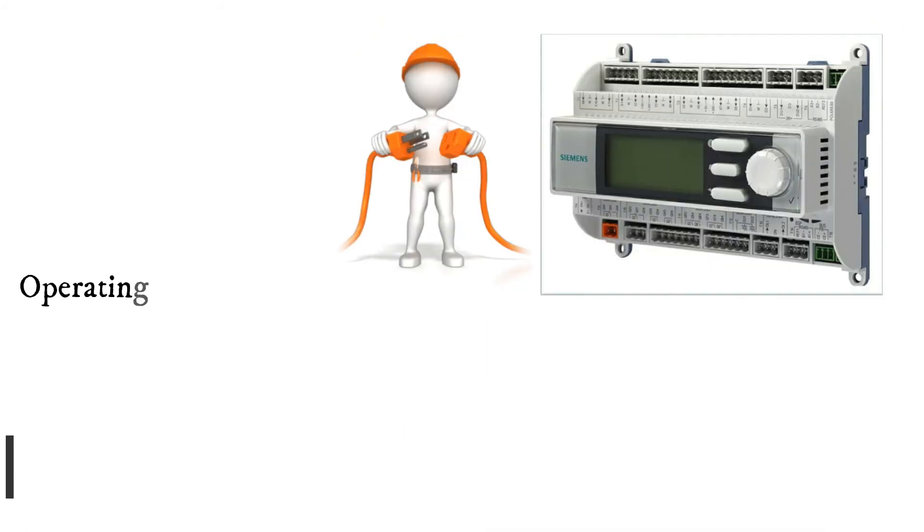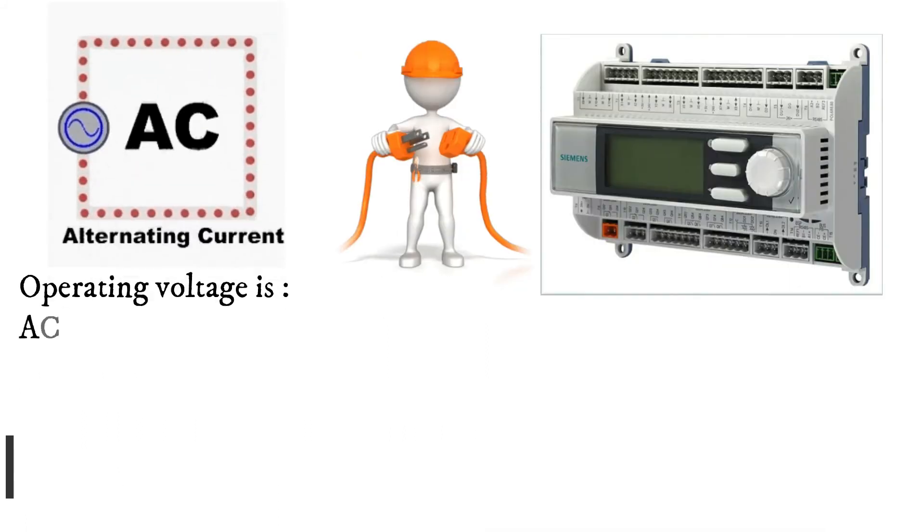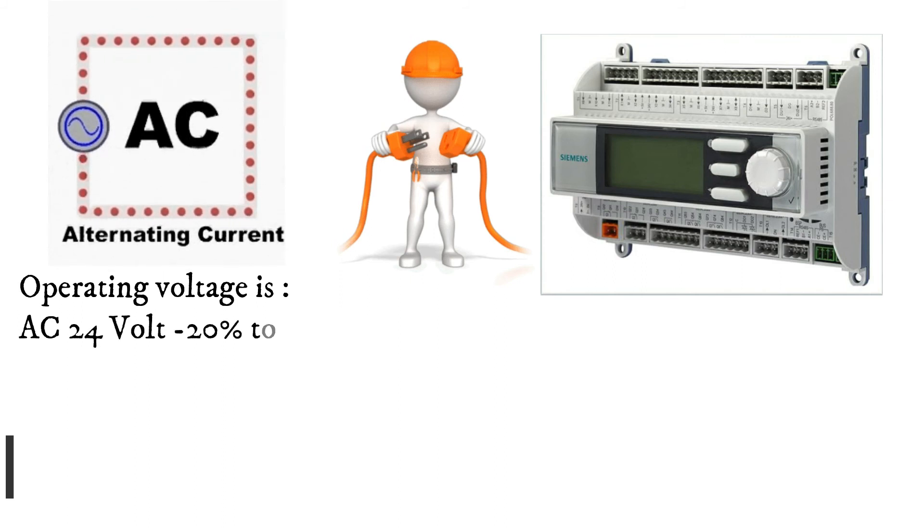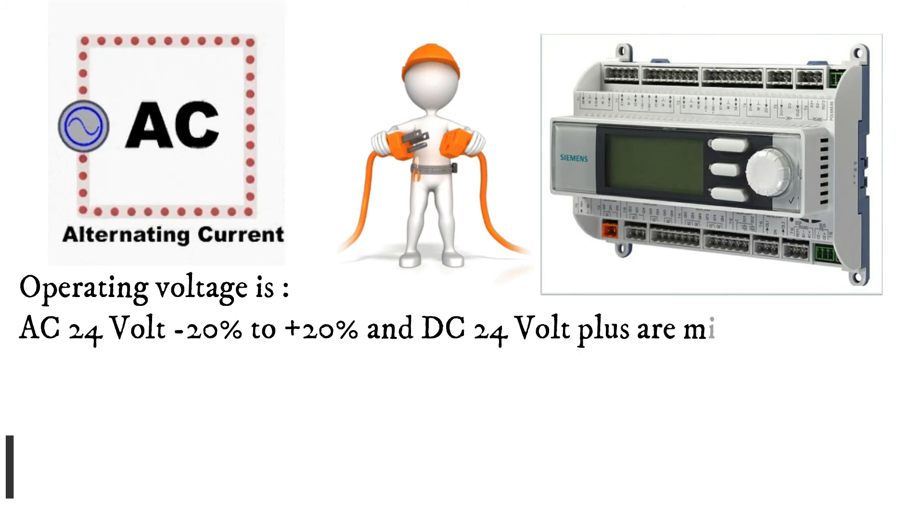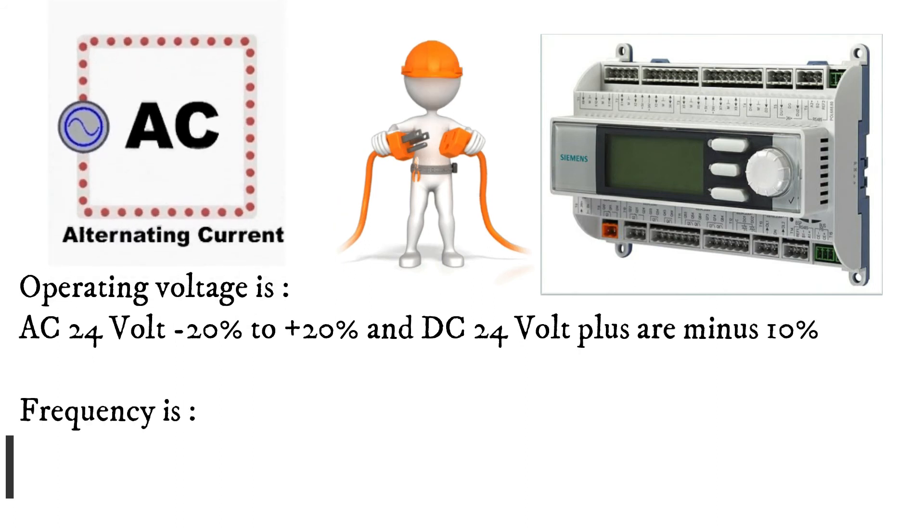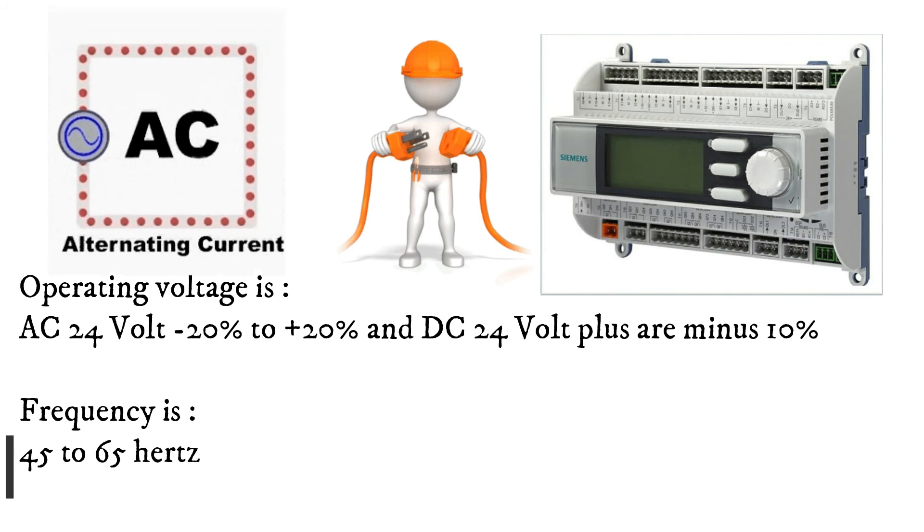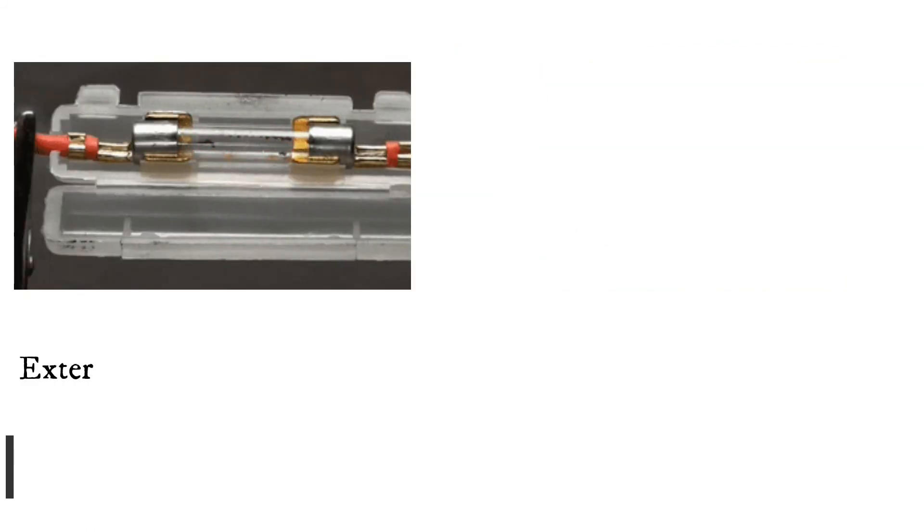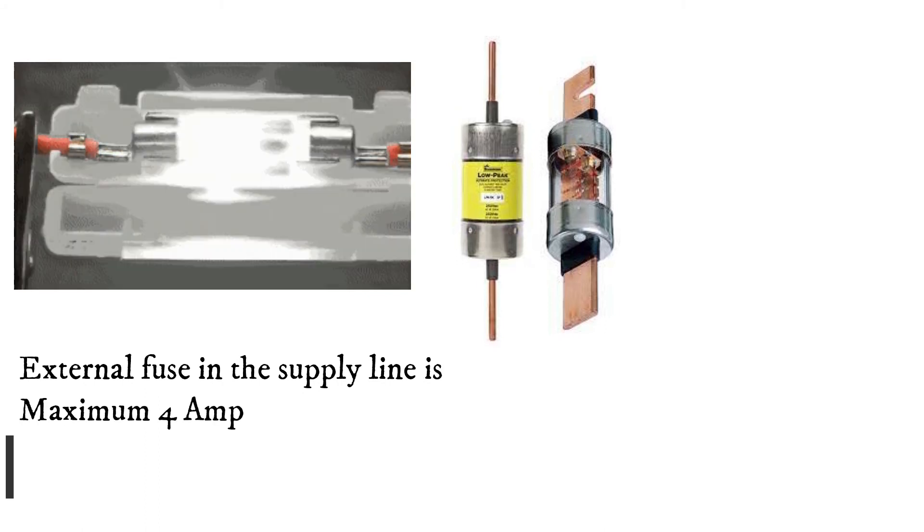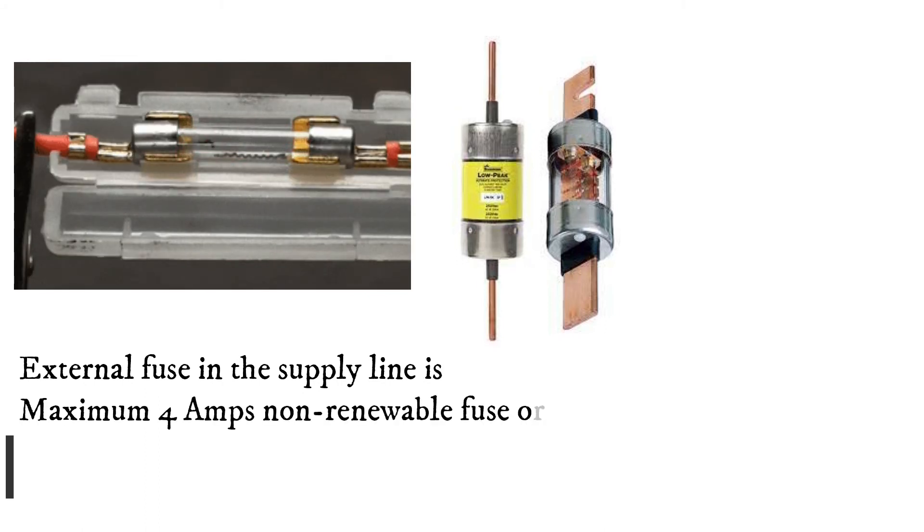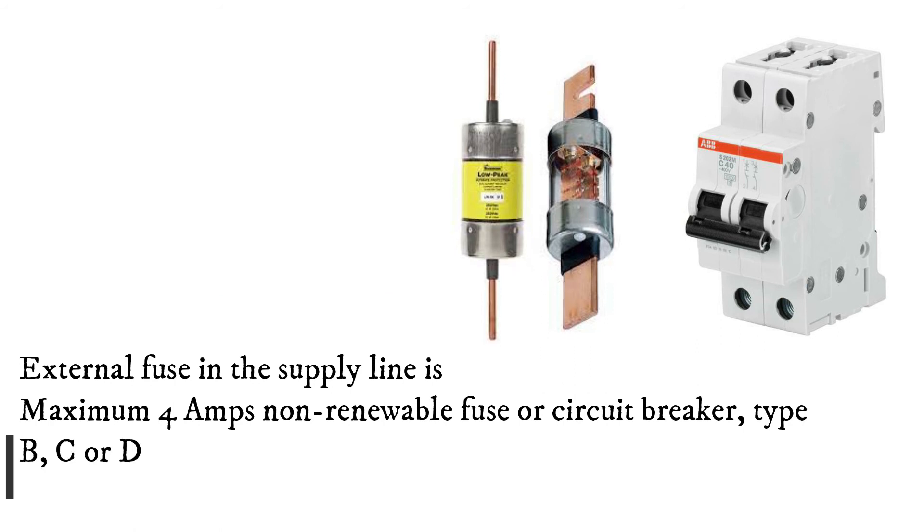Operating voltage: AC 24V -20% to +20% and DC 24V ±10%. Frequency: 45 to 65Hz. External fuse in the supply line: Maximum 4A non-renewable fuse or circuit breaker, type B, C or D.